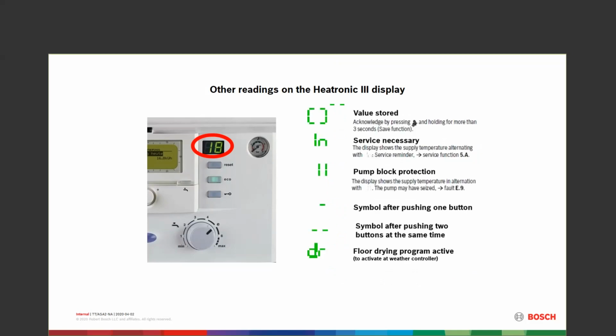The value stored brackets will show up anytime you change a service function or change anything in there. You're going to press that little chimney sweep guy and hold it for more than 3 seconds. It's going to save whatever function you've changed and save your changes. The two brackets show up and then go right away. So if you don't see the brackets, save it again. If you do see the brackets, you've saved it. You can go right back in and see if you've saved what you thought you did. That makes good sense.